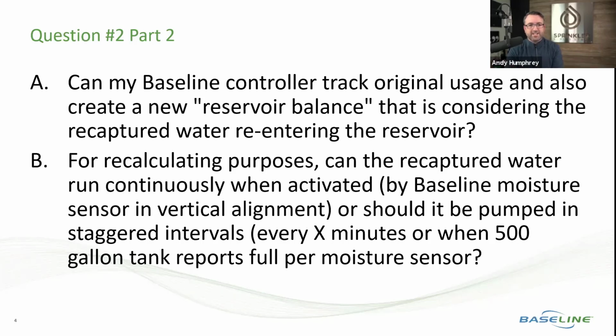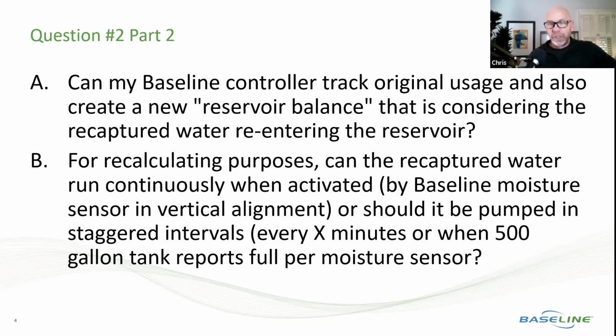What we really need to do is look at this in terms of how we want these tanks to operate, at what level do we want to use each water source, and then use the pressure transducer. That's what I would recommend, to set those points so that we have a truly on-demand system that's not actually using math to run, but it is tracking the usage, and it's in real time, which is the benefit, so we don't have to do the math.